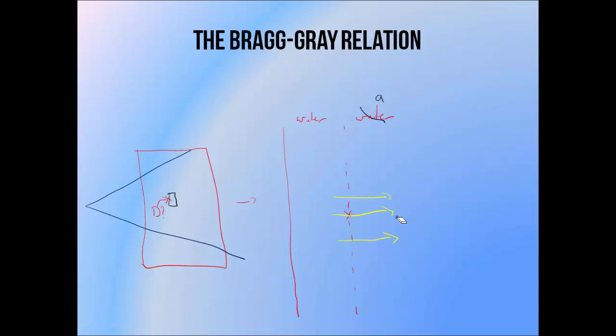When we replace the water below this point with an ionisation chamber — so with a volume of air — it changes how these secondary electrons behave. They'll travel further through air than they would through water, and they'll lose a different amount of energy. The purpose of the Bragg-Gray relation is to allow us to use the amount of energy measured in this region of air to work out how much is being deposited at the point at which we wish to know the dose.